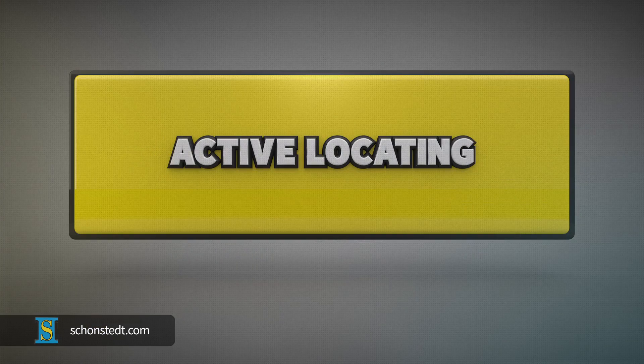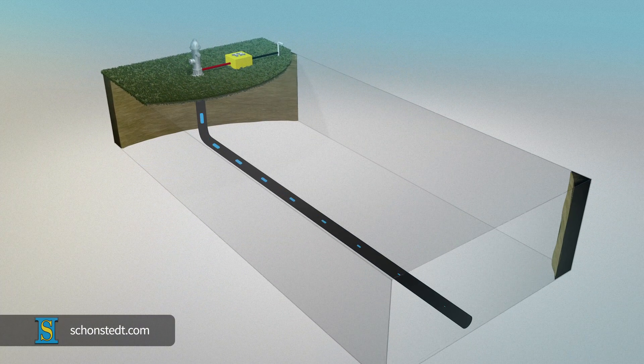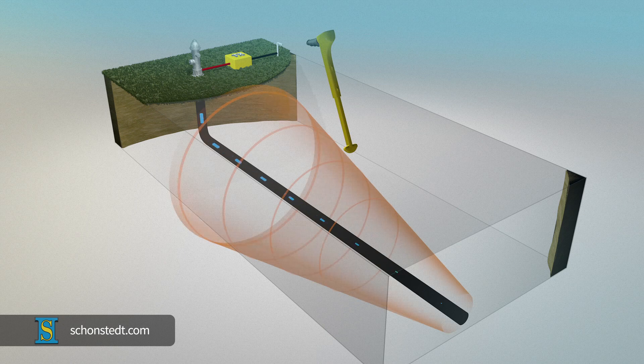The first method is known as active locating, because a transmitter is used to impose the circulation of an electric current on the pipe or cable, and a receiver is used to detect the field created by the current.